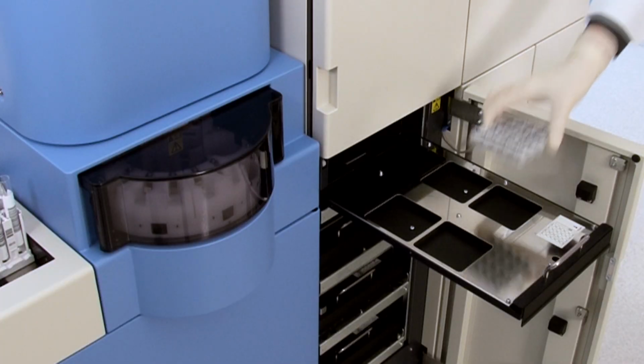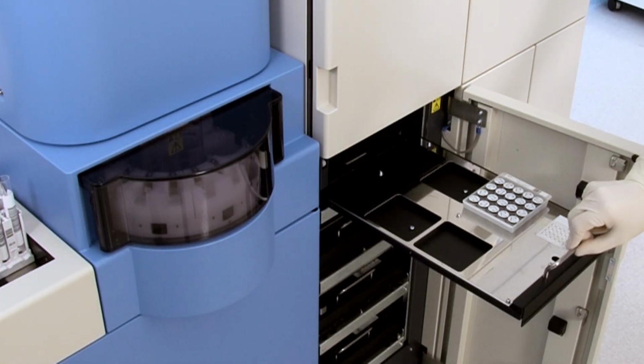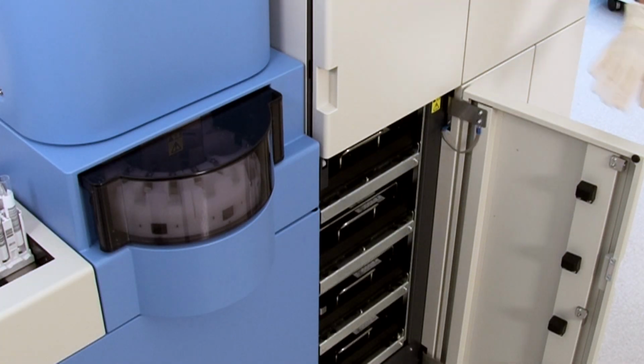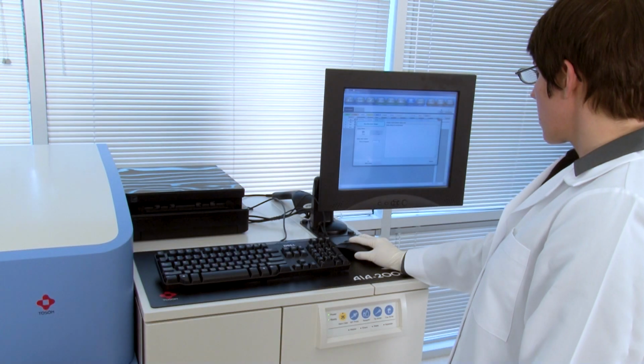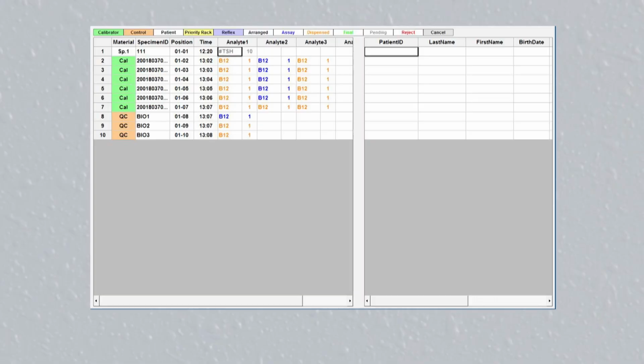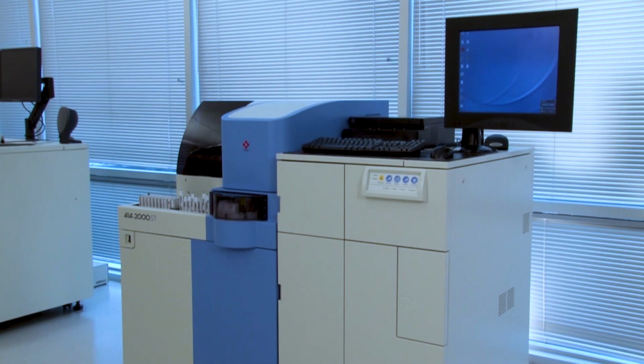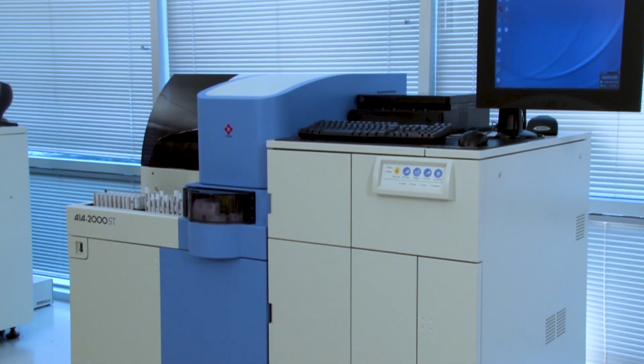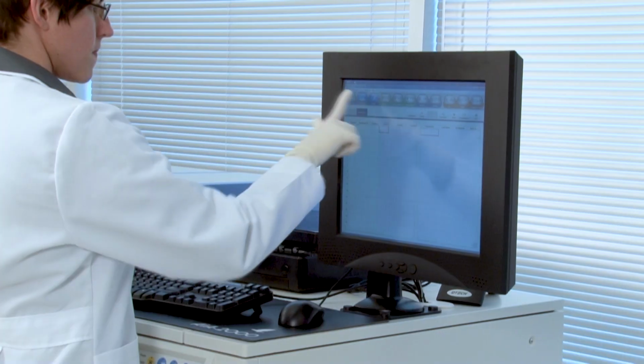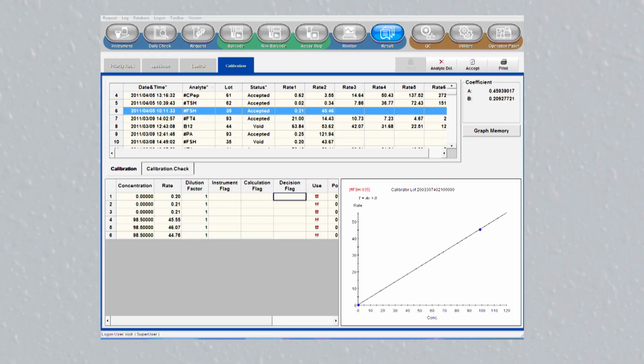Once the reagent tray is loaded in the reagent drawer, the barcodes on the trays and sample cups are read, and the inventory is stored in memory for easy review by the operator. Color coding on the reagent inventory screen indicates whether or not the lot number on board is calibrated. Previously assayed test results can be calculated after calibration if the operator chooses to do so. The AIA 2000 stores calibration curves, and calibration stability is good for 90 days on most assays.